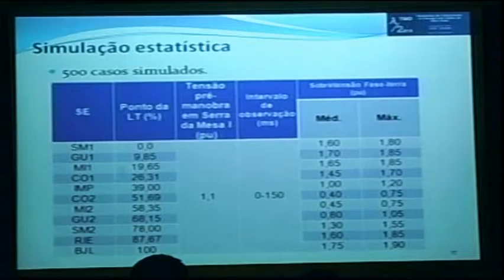Here we have the results of our simulation, the statistical result, and we have reached 1.9 pu as an average level, 1.75 pu at the end of the line. Here is the end of the line. You can notice that throughout the line, this will be the highest overvoltage, but in the middle of the line we have 0.75 pu, because in a permanent regime, the sustained voltage for the half wavelength in the middle of the line is close to zero. It's a little above zero, 0.10 pu. So you only have the transient disturbance that raises this voltage, and then it goes back to a smaller value. So this is how the half wavelength behaves.